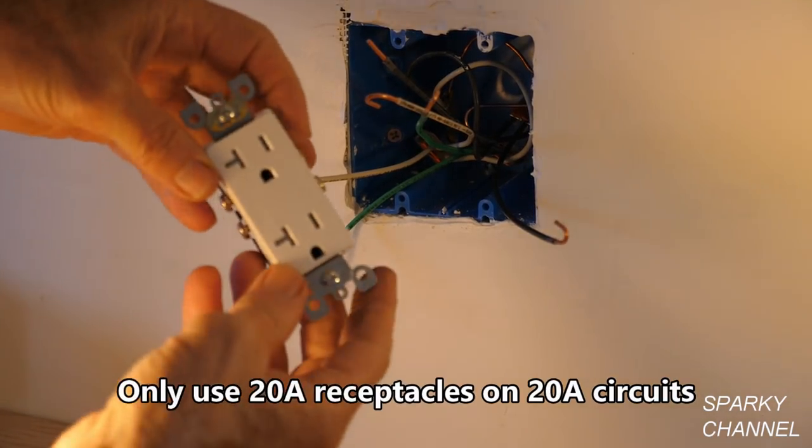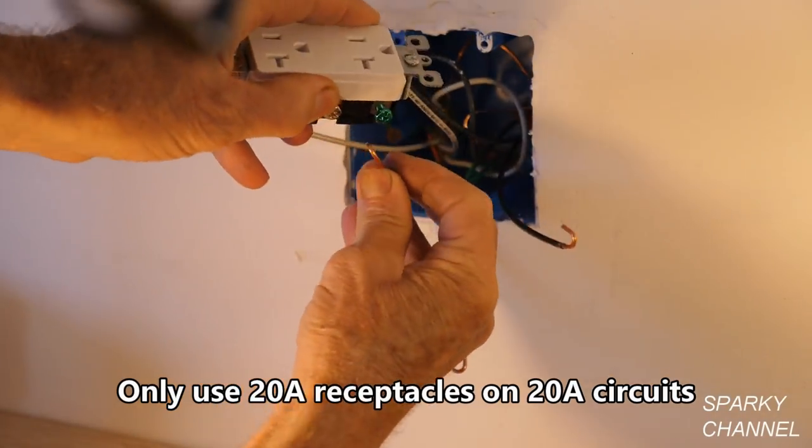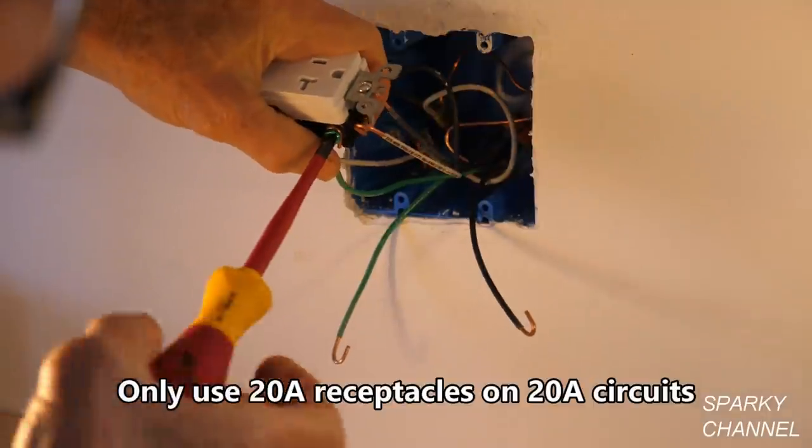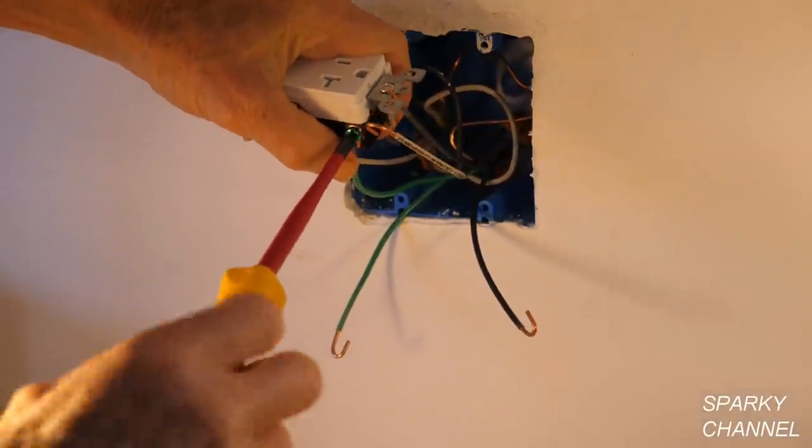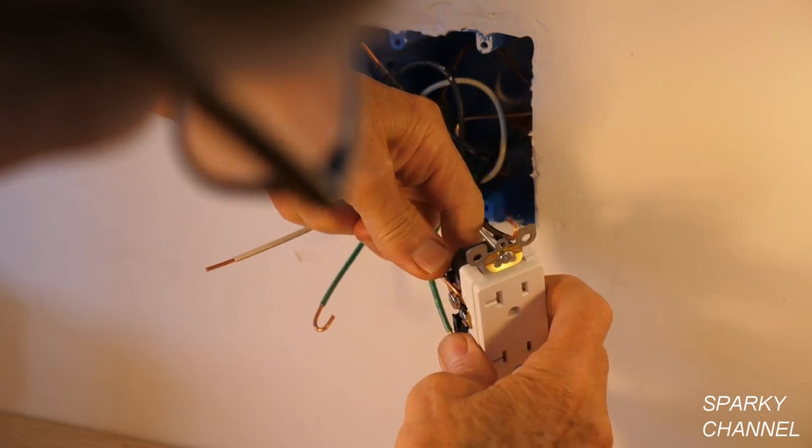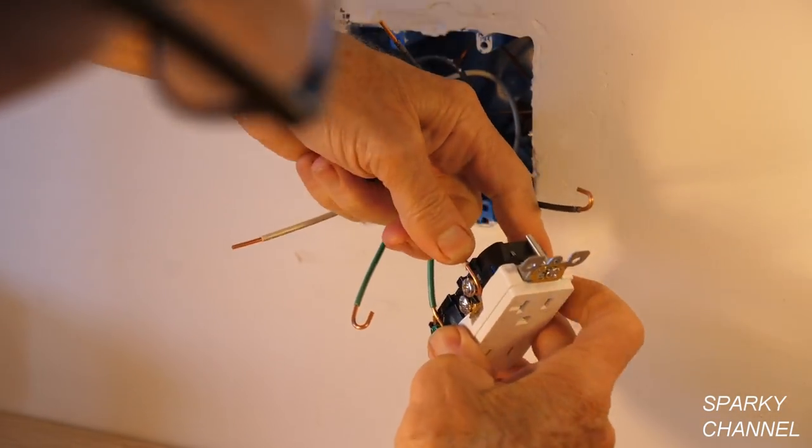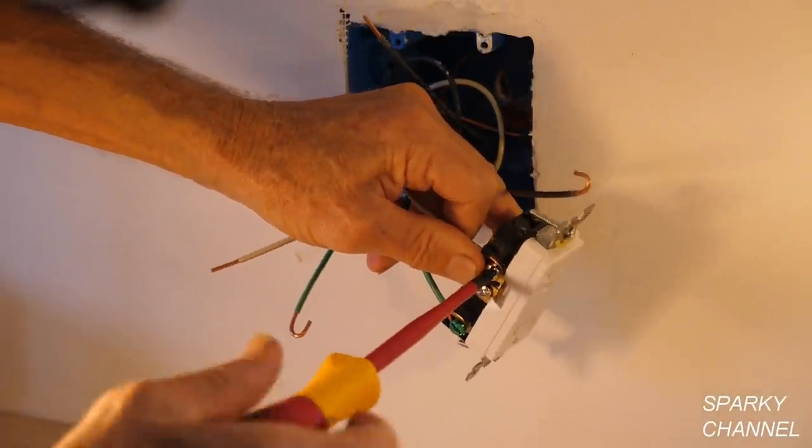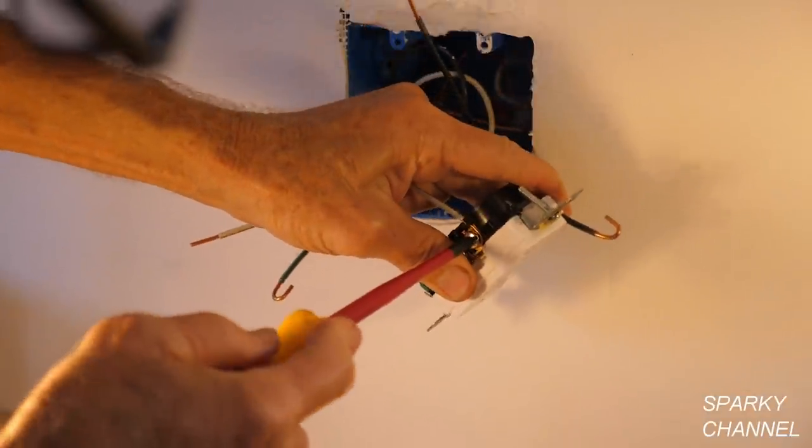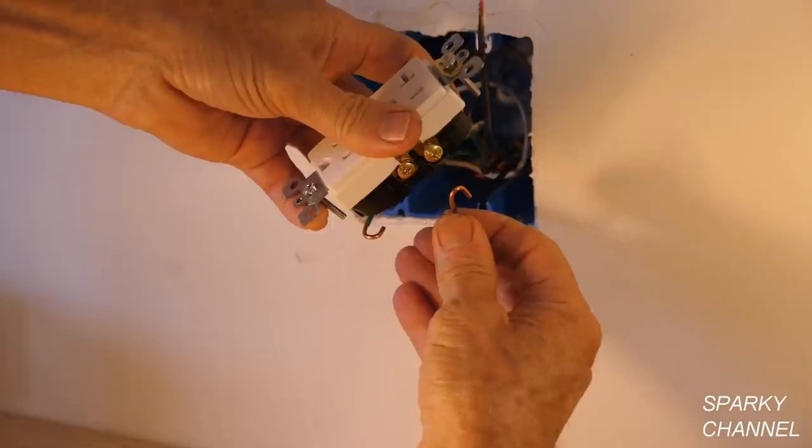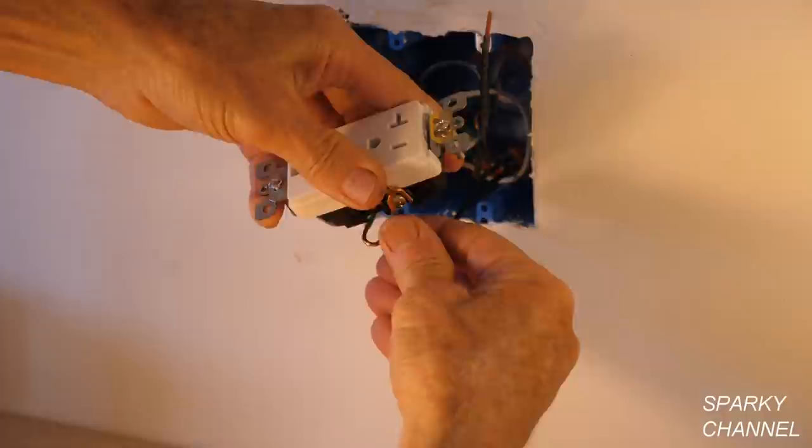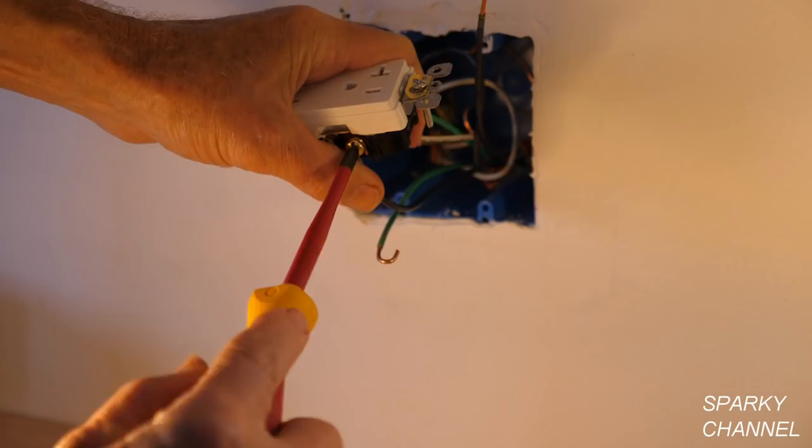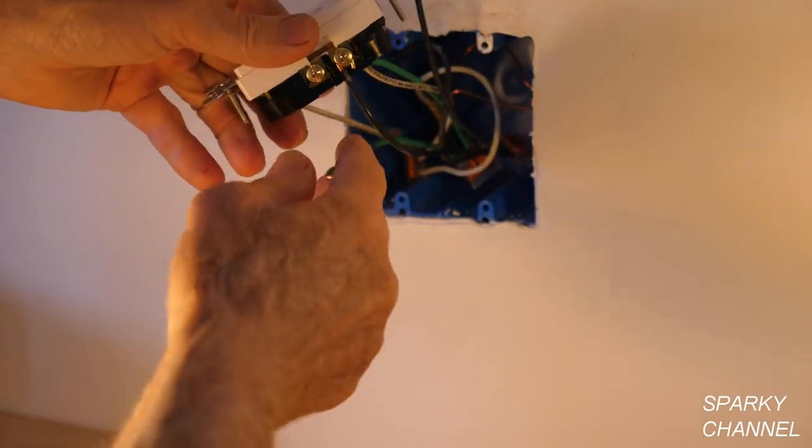So let's get started wiring this receptacle. I'm going to take the ground and I'm going to put it around the green terminal and tighten it down securely. So now I'm going to take the neutral and I'm going to go around the silver terminal. I'll crimp the wire and tighten it down securely. Take the black wire, put it around the terminal, crimp it, and secure it well.